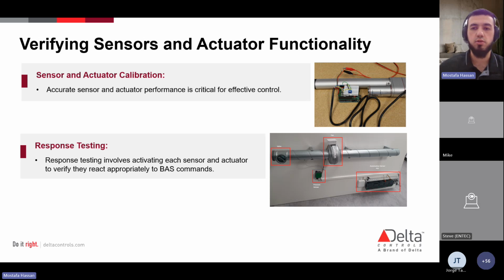Response testing is where you're activating each sensor and actuator to verify they react appropriately to the commands from the automation system. For example, testing might confirm that a temperature sensor accurately triggers a fan or that a valve opens when the system demands. This step is actually going to confirm that devices are responsive and ready for operation. So you can't just write up the sequence of operations, set the hardware out in the field, and walk away. You have to actually test the things. Things go wrong all the time. Equipment can malfunction from the factory, or if not tested properly.